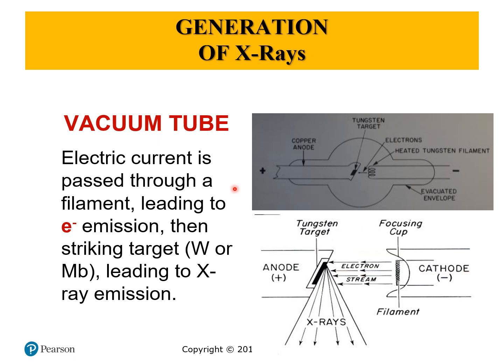Now there is one more thing. We can also have around it a shield of lead with only some openings to specify in which direction the X-rays go, and we want them to be straight. So you can have something like this, with just this opening, allowing the X-ray to go only in one direction. And they need to be parallel. That also increases the performance of your X-ray image.